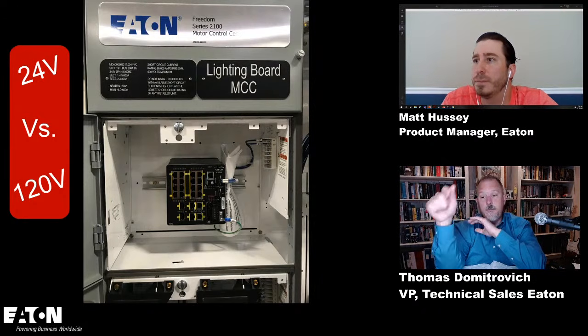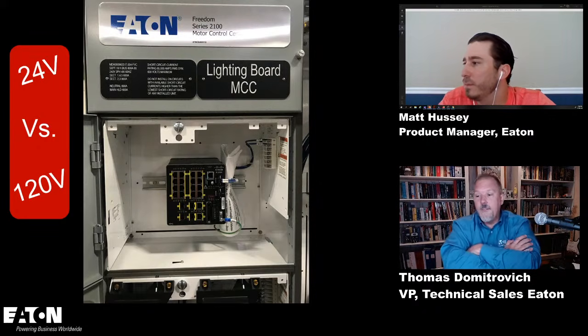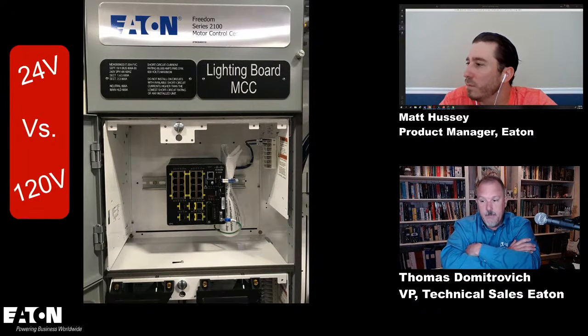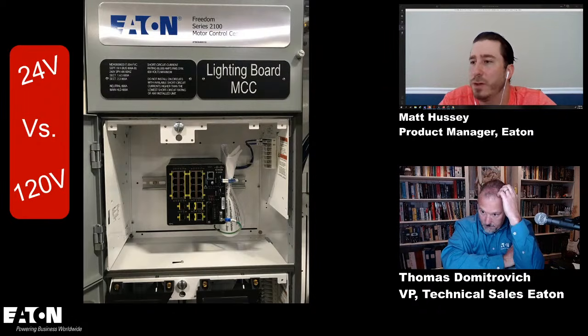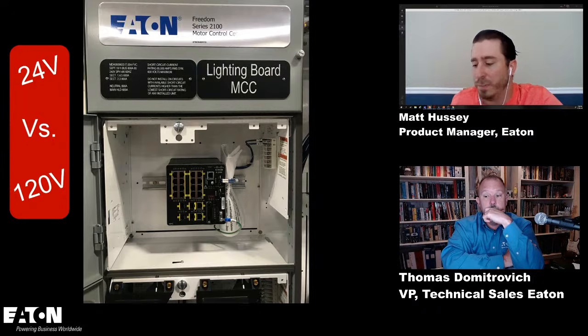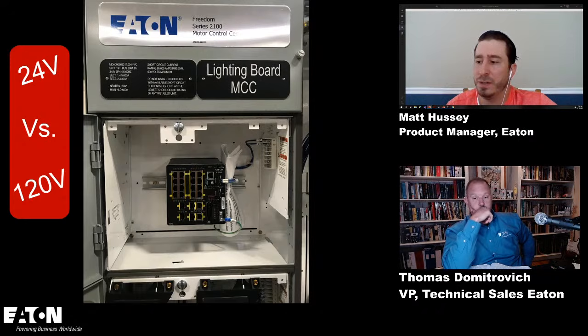Right. So Mr. Ford has a question. If I am specifying a contractor to retrofit an existing motor control center bucket and use it as a pass-through to a new remote-mounted variable frequency drive, what's the best way to do that? I would try to get a feeder unit, or an aftermarket unit that has either a breaker or a fusible. You might need to check with the drive as to what branch circuit protection it needs. But then you basically just add in a separate unit there to feed that. Because usually the MCC isn't designed so that you can just lug off of the bus and feed out to that. You're going to have a unit to feed out from that compartment.